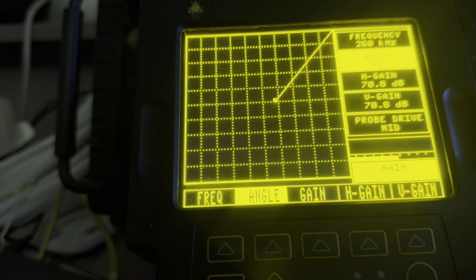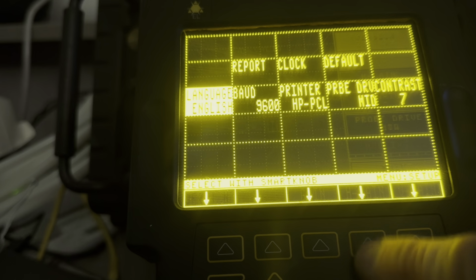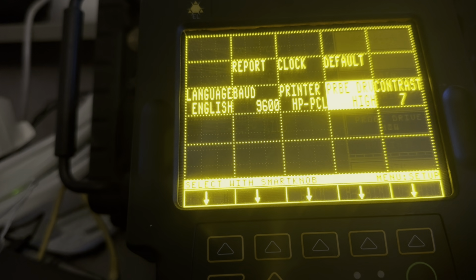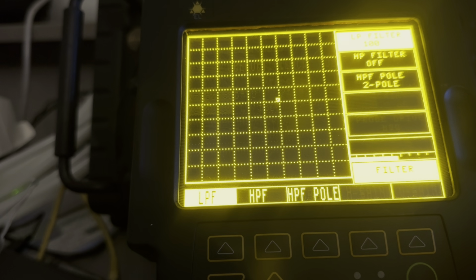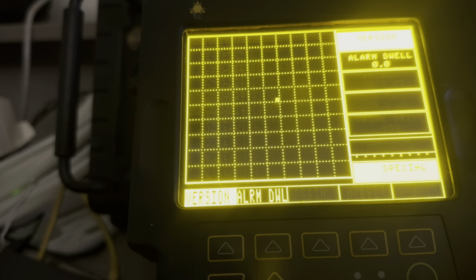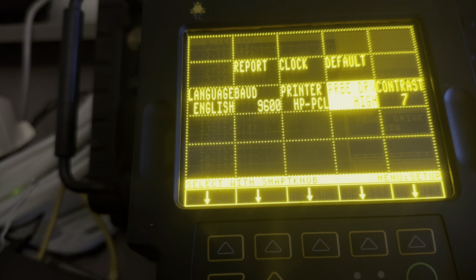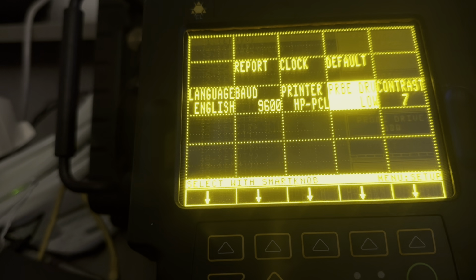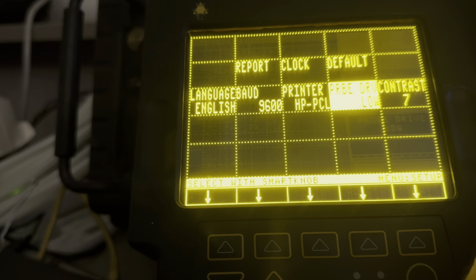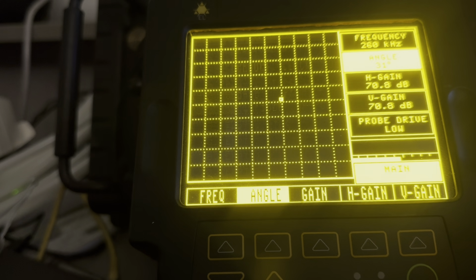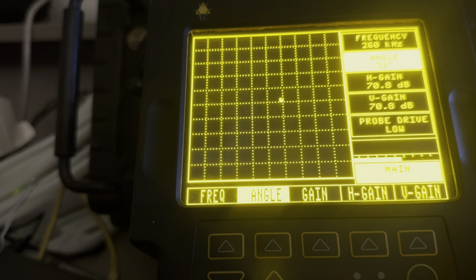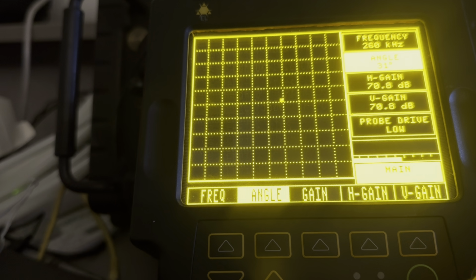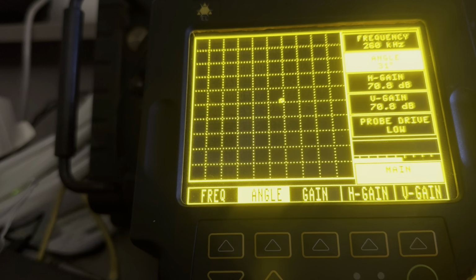Well, let's go and try a couple things that won't work at all. I changed the drive voltage to high. That doesn't do it. You know, sometimes this drive voltage does weird things. Just go check them all out. And even if they're the obvious wrong choice, at least if you try them out, then you'll know that you ruled that option out. And it's maybe one more reason that leads to your decision that you need to try some other variables or settings to save the probe's life. Because this is a perfectly good probe.